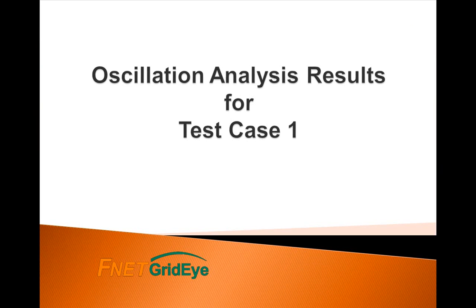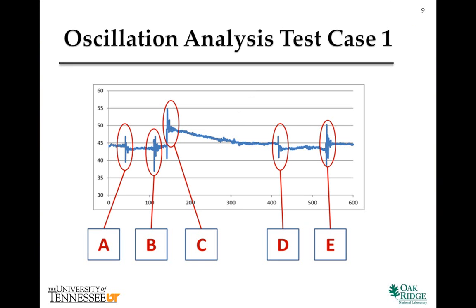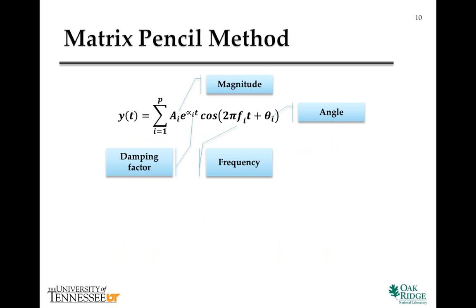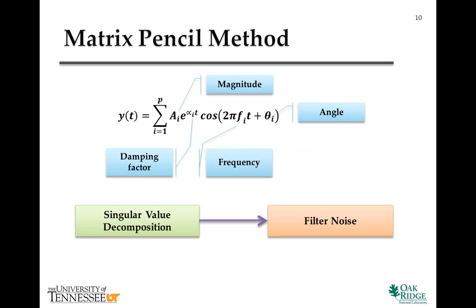In the second section, we will discuss the results of the oscillation analysis test case. For test case one, there are five ring-down events in the 10-minute data. The matrix pencil method is used to estimate the oscillation frequency and damping ratio. This method uses singular value decomposition to provide an effective way to filter noise.